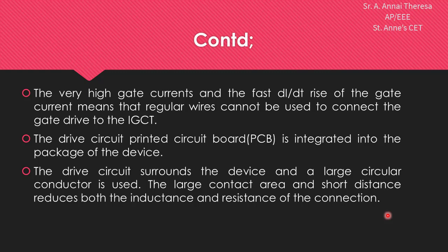Due to the very high gate currents and the fast rate of rise of gate currents, we cannot use regular wires to connect the gate drive to the IGCT. Therefore, the drive circuit PCB is integrated into the package of the device — it is inbuilt. The drive circuit surrounds the device and a large circular conductor is used. The large contact area and short distance reduces both the inductance and resistance of the connection.